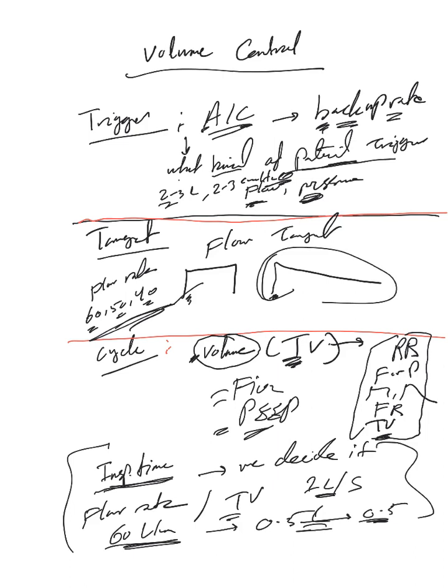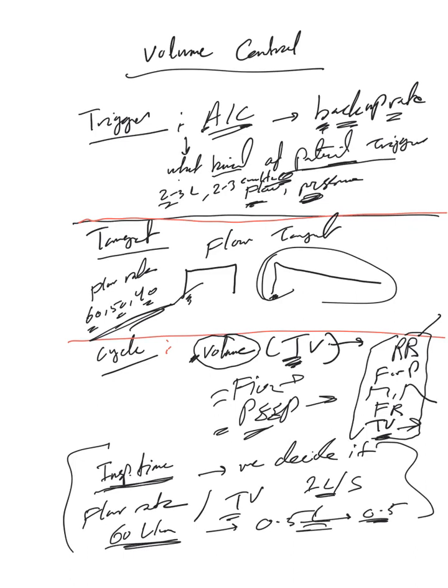the decelerating ramp and they will pick flow trigger. So sometimes they don't ask you. If you want just to be very thorough, you have to provide all these. But for sure you need to provide the backup rate, the backup rate and tidal volume, of course FiO2 and PEEP.